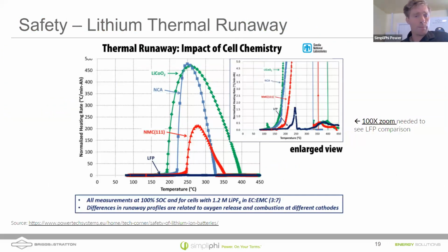This is from a national lab, confirming how LFP battery chemistry is safer. On the left, the vertical axis shows the normalized heating rate, basically how quickly heat was released from a battery when forced into thermal runaway. If you look at the scale for NMC, NCA, nickel manganese cobalt oxide, and lithium cobalt oxide batteries, they're on a much higher scale than LFP. LFP is actually just down on the axis, a very slow release of temperature even when forced into thermal runaway. Again, this is from Sandia National Labs.